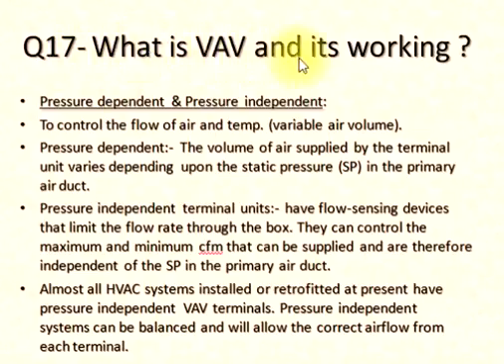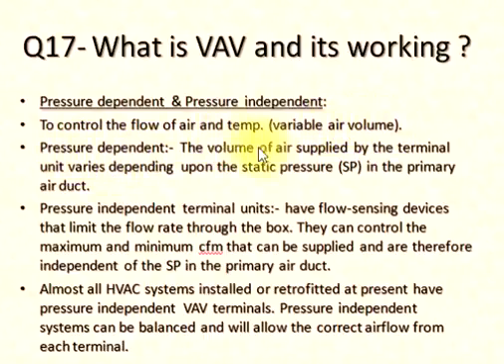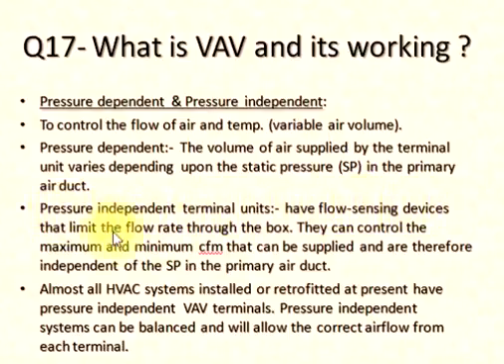Q17: What is VAV and its working? Pressure dependent and pressure independent — used to control the flow of air and temperature. Variable Air Volume: Pressure dependent — the volume of air supplied by the terminal unit varies depending upon the static pressure (SP) in the primary air duct. Pressure independent — terminal units have flow sensing devices that limit the flow rate through the box, controlling the maximum and minimum CFM supplied, independent of SP in the primary air duct.